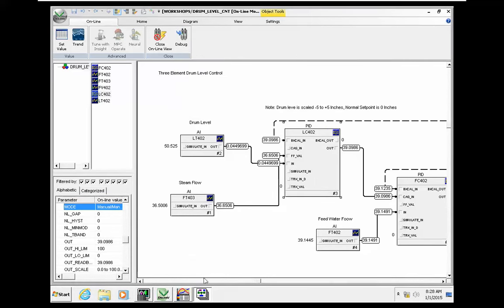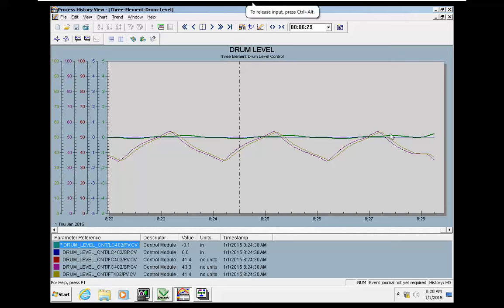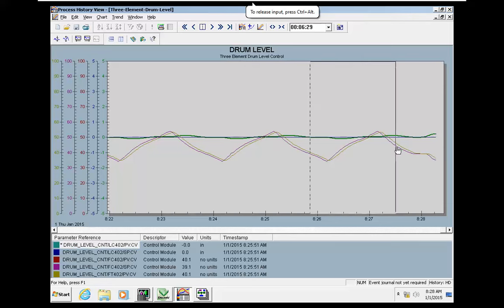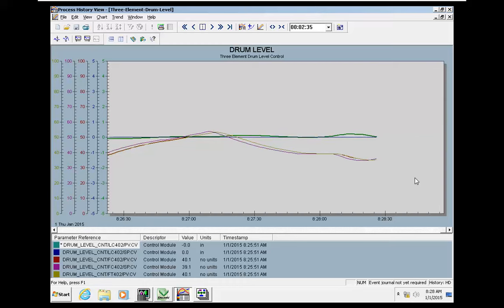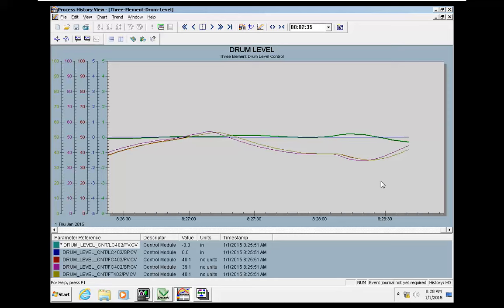Let's see what's the effect of feedforward. You can see that when we disable the feedforward, the control quality is damaged or reduced. We are in automatic, let's check several cycles.